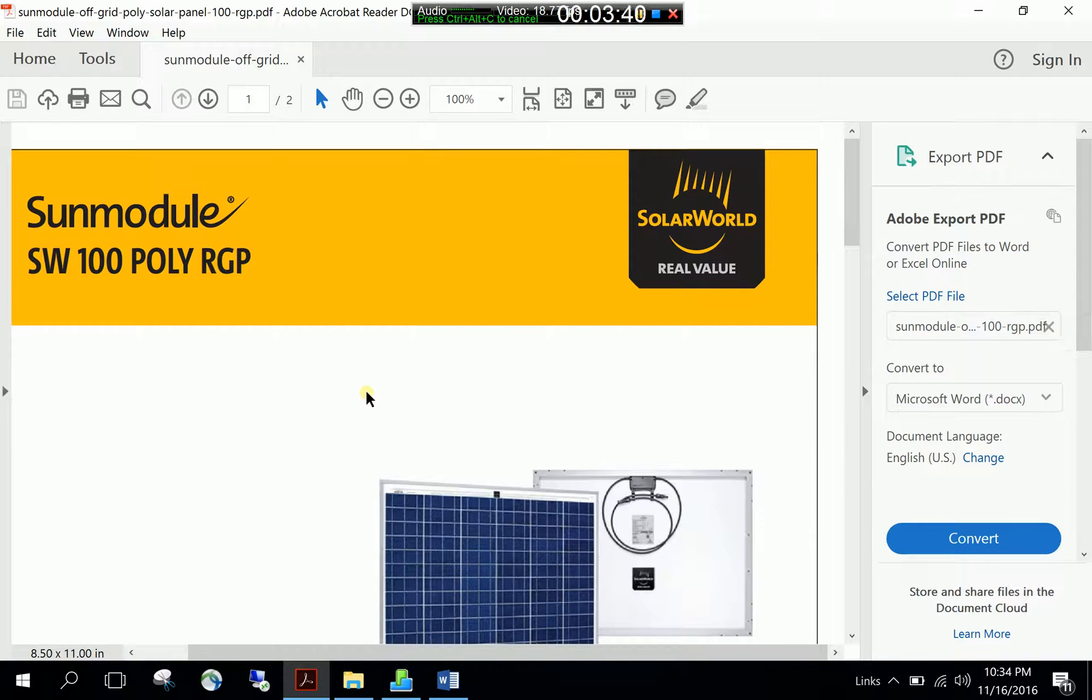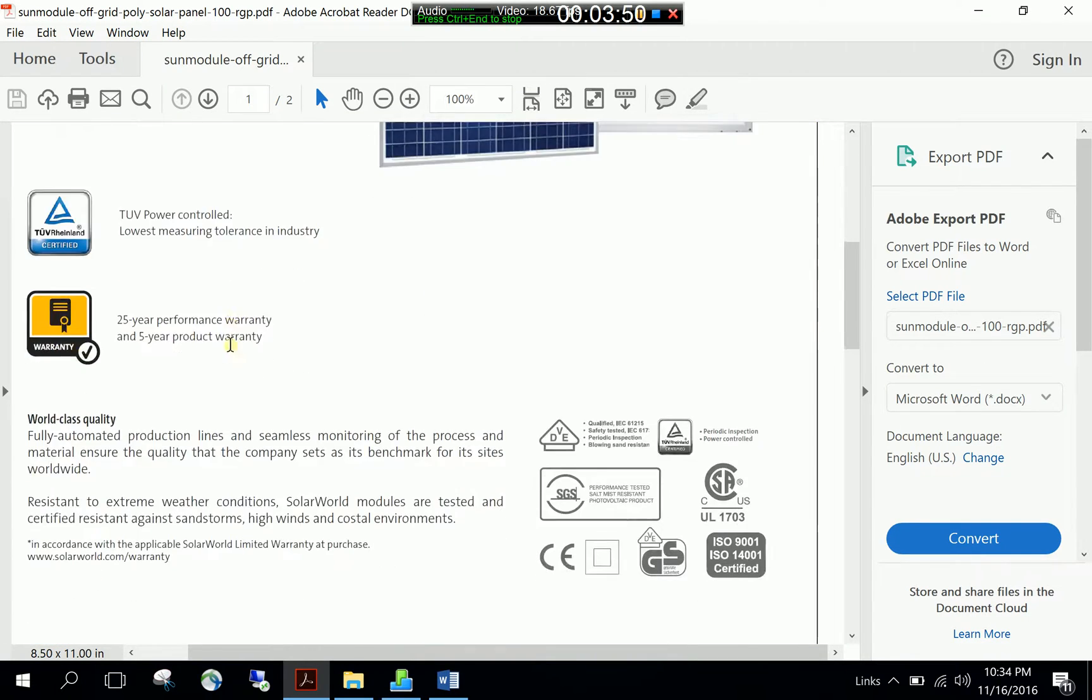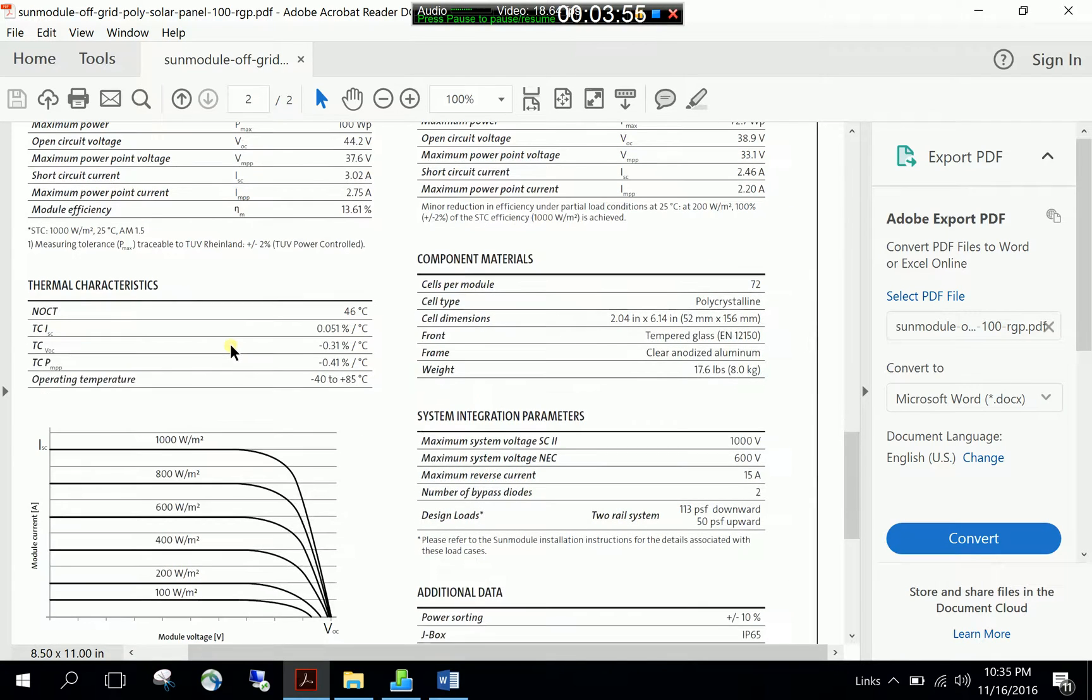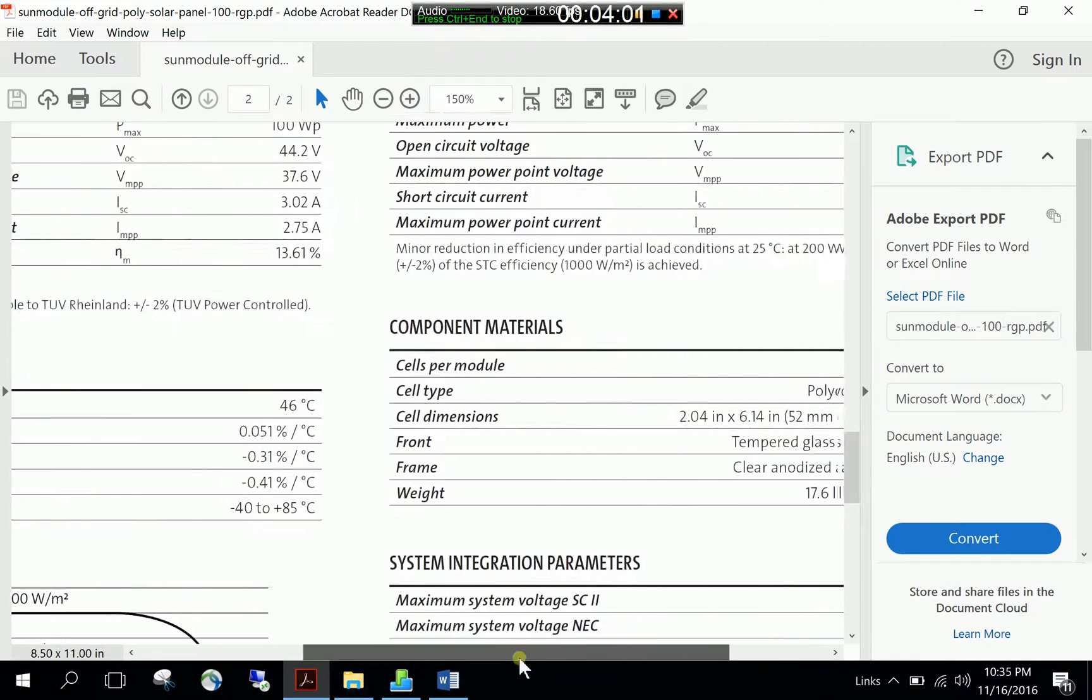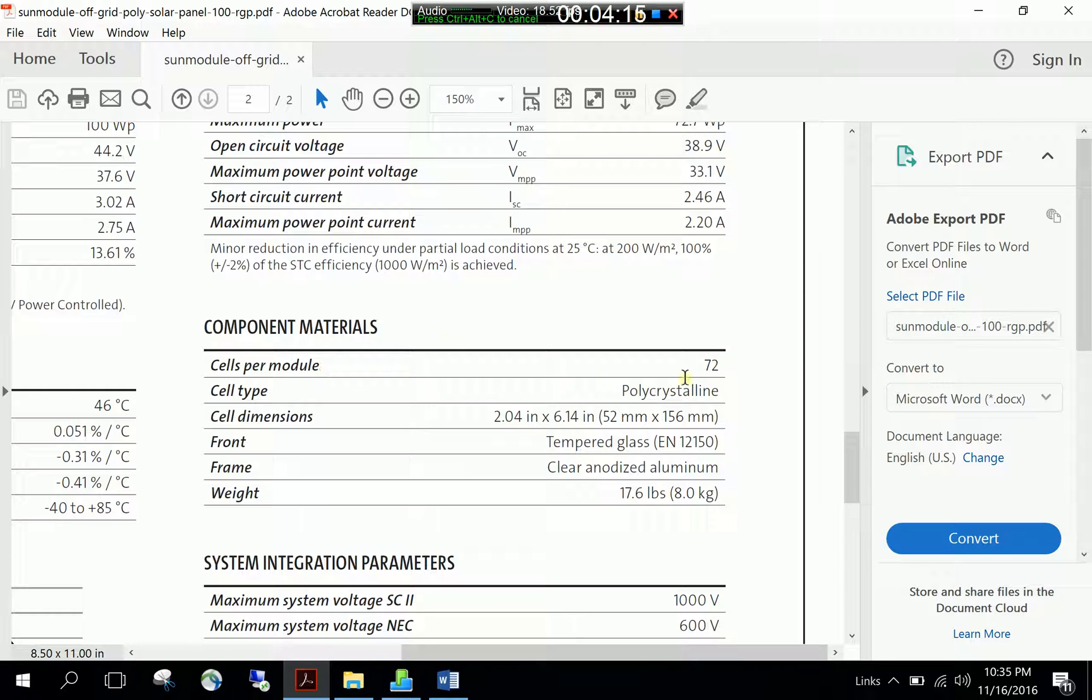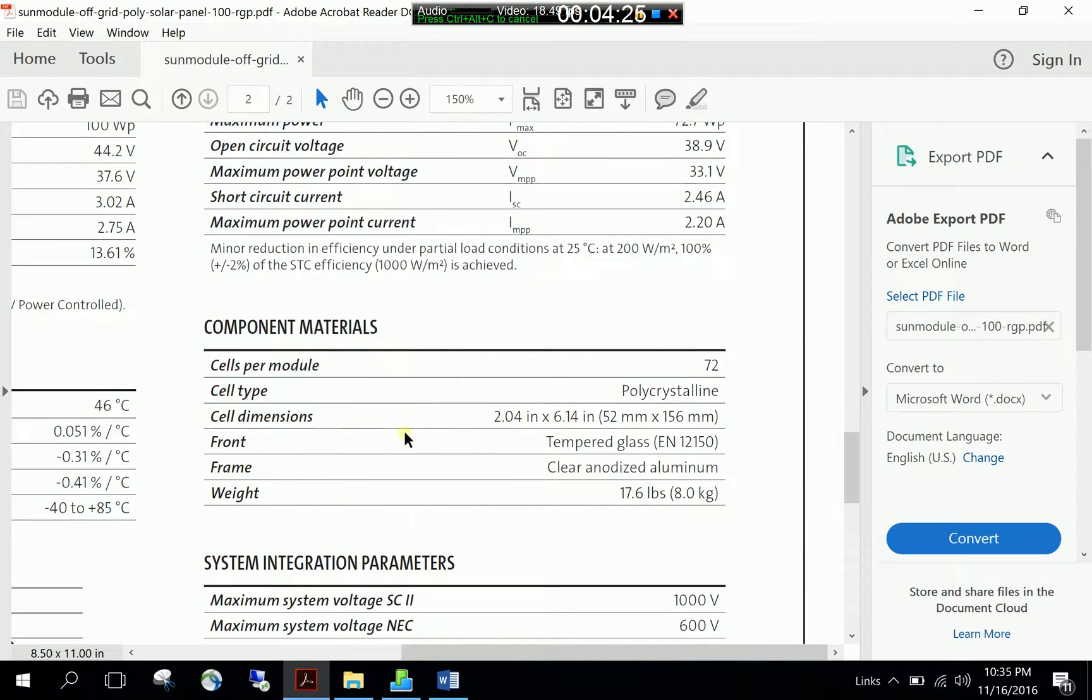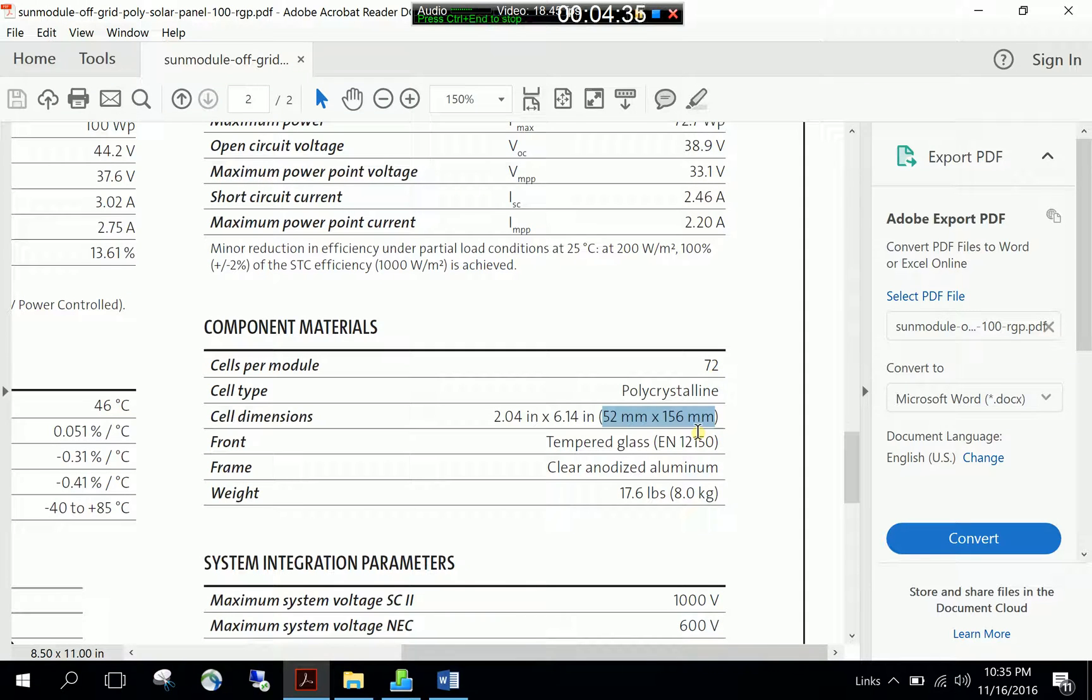Here you see a sample polycrystalline PV module from Solar World and it's about 100 watts as you see in the name. Let's scroll down to the second page and focus on the geometric properties. I will focus on the geometric properties here related with the cell dimensions and cells per module. As you know, solar PV modules are composed of individual solar cells. This module, for example, has 72 solar cells connected in series electrical connection. And I have the cell dimensions.